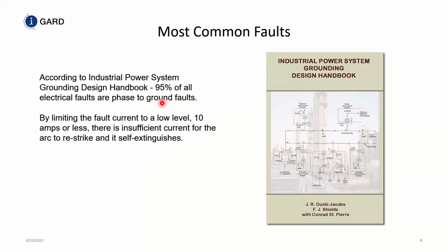So I don't know if any of you have this book, but it's an excellent book, Industrial Power System Grounding Design Book. And according to Dunki-Jacobs, Mr. Shields and Mr. Conrad St. Pierre, who incidentally, as Miriam said, I've had 3 decades of experience in the field. I met all of these gentlemen, and I can't hold a candle to what they know about grounding. According to them, most faults begin as single phase to ground faults, and they propagate to phase or 3-phase fault.